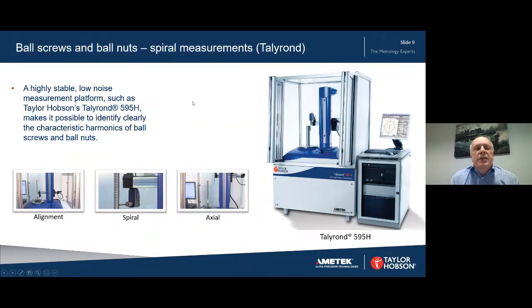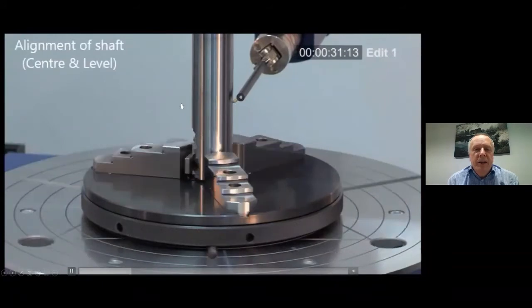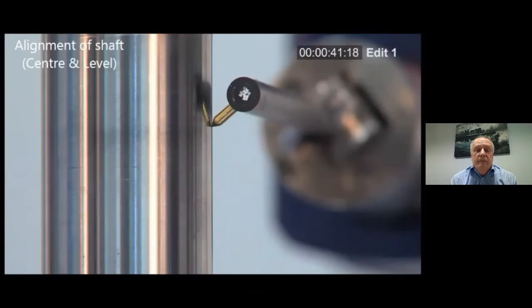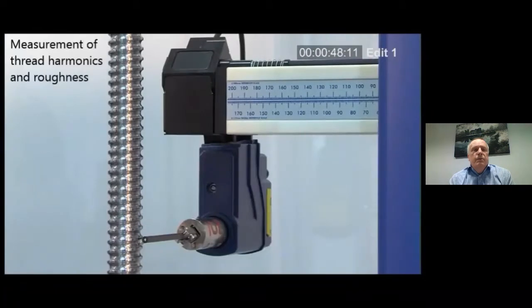The Talyrond is a highly stable and low noise measurement platform and it makes it possible to identify clearly the characteristic harmonics of ball screws and ball nuts. If we don't have a low noise platform, we can't measure harmonics correctly. So we'll have a look now at alignment. This time instead of aligning on the thread, we're aligning on the shaft, and when we measure the thread we can see it in relation to the shaft. The centre and level routine is now finished, and we proceed to measure the thread harmonics.